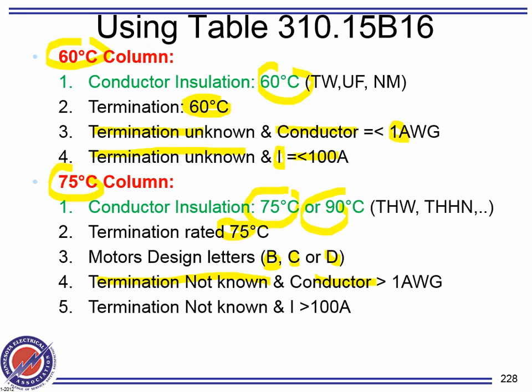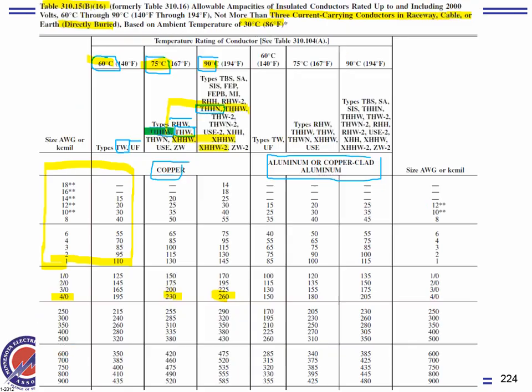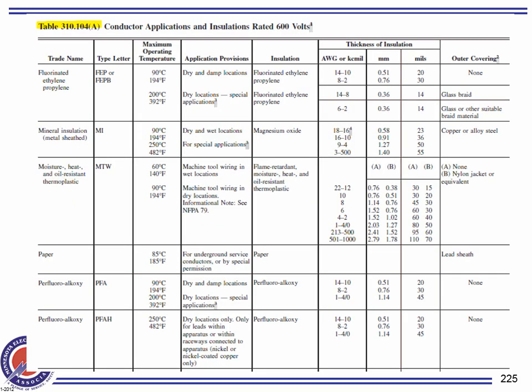How about if the terminations are unknown and the piece of equipment says 100 amp piece of equipment? Where do you go? And your conductors are rated THHW or THW, you go to 75. These are the rules for using the 75. So once you go to the 75, gentlemen, basically 75 starts right here. From here on, this is when we start using 75. Does that make sense? From here on, you start using the 75. But don't forget the rules, though. The rules for the 75.